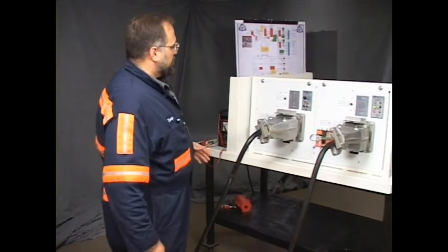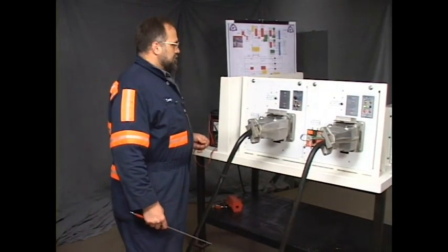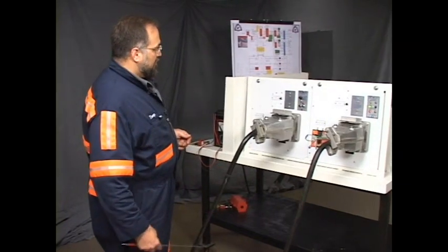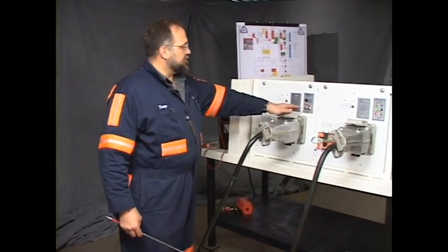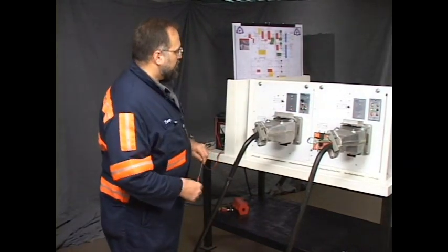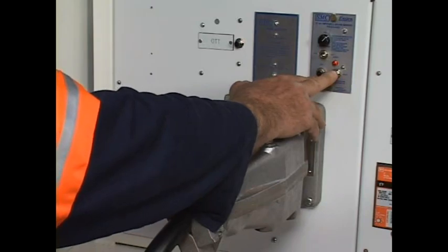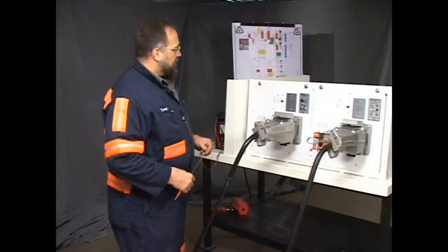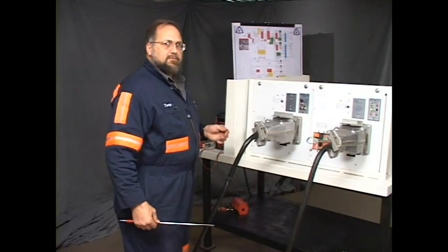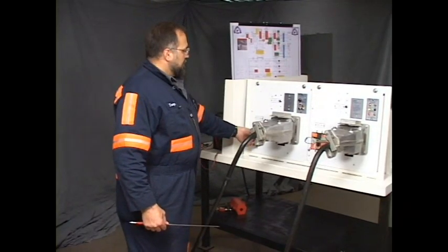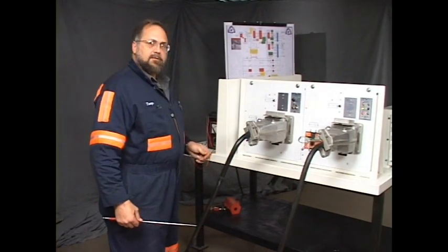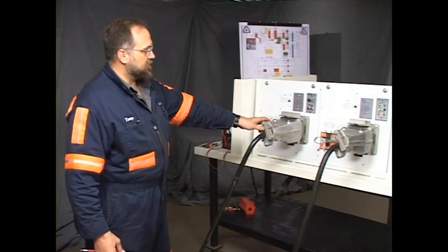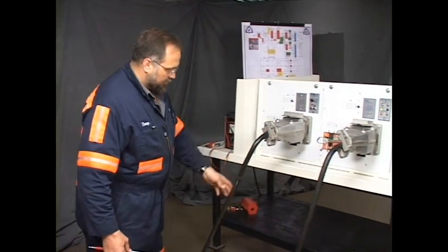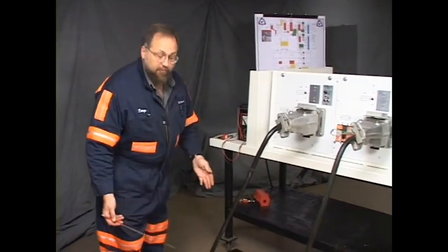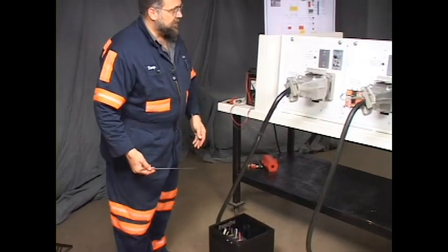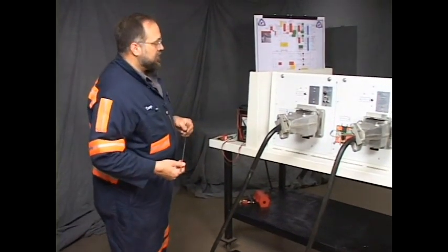This is what you would see both at the testing center or in a workplace. When you first approach the power center, you have a monitor light and a tripped light showing. Well, normal operation would be to press the reset switch, and it did reset. I don't know if the audio can pick it up, but we could hear a relay close. The GCS1 contacts are now made, and then you could latch and set the breaker. Okay, this is the power circuit plug, the cat head as it's called, the cable going to the machine. And should this be a real power center, this machine would now be energized. Okay, that's what we want to have. But on our problem, that's not happening.